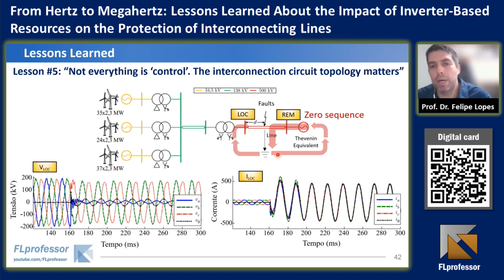So the lesson 5: not everything is control, but the interconnection circuit topology matters. Basically here, what we know is that zero sequence contribution comes from the system and it returns through the grounding points. And this is not a characteristic of the control. People for a long time were believing that these problems, this alignment between the three-phase currents, were related to the IBR controls, and they are not. They are related to the circuit topology. And it is very important to understand that we can have overcurrents and the zero sequence elements are still very reliable in this type of system when this contribution has a path to flow and to enter again here in the line.